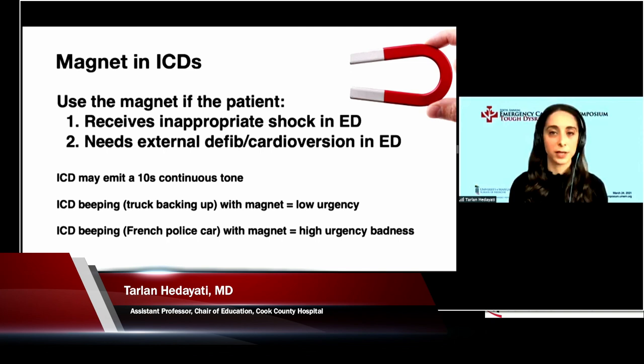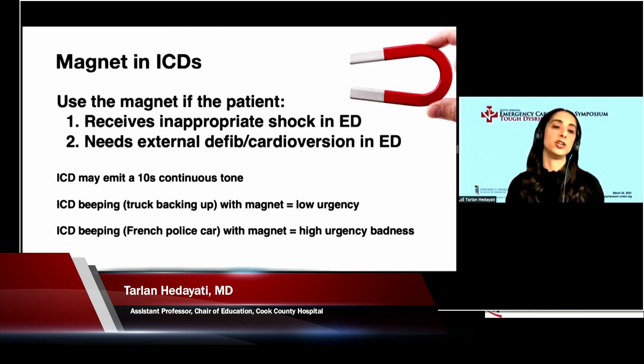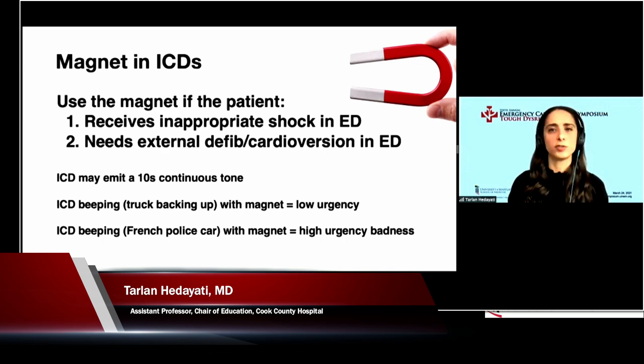If you hear a sound like a truck backing up—beep, beep, beep—that's a low urgency alarm, just indicating something's going on, not a big deal, don't worry, I'm okay, but just a heads up. Typically when we interrogate the device at that point, we get an indication like, oh, maybe the patient got a cardioversion or defibrillation from the device.